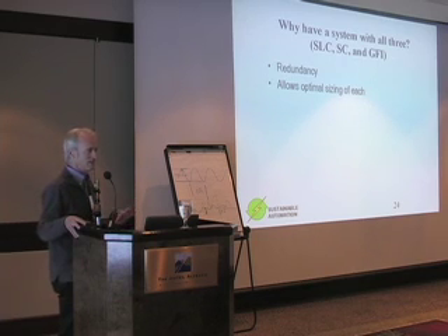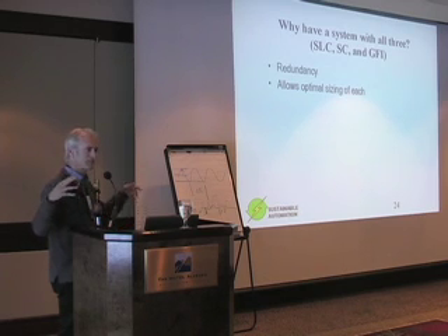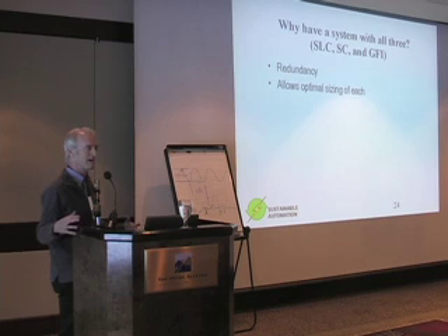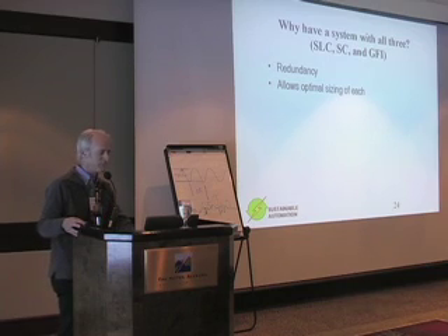And as I touched on before, the synchronous condenser inherently, because it's this big mass of copper and magnetic steel, has the ability to deliver much more fault current than a typical inverter. So it provides additional benefits as well. I got the 5-minute warning a few minutes ago, which works out perfectly because that was my last slide. But we have some time for questions if there are any.